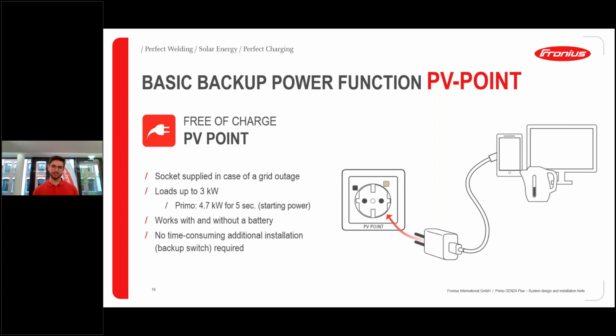Of course, it's not recommended to use a simple wall socket. Please also make sure that it is RCD secured. So there are RCD integrated wall sockets, or you can of course separate those two. But it's very important to have a secure single phase line to this PV Point. And then the PV Point will activate as soon as the grid is gone. And this PV Point will be supplied with a nominal power of up to 3 kilowatt. For a short time, we can also supply a little bit more. So as we can read here, for 5 seconds, we can also supply 4.7 kilowatt. So even higher power classes can be supplied here.